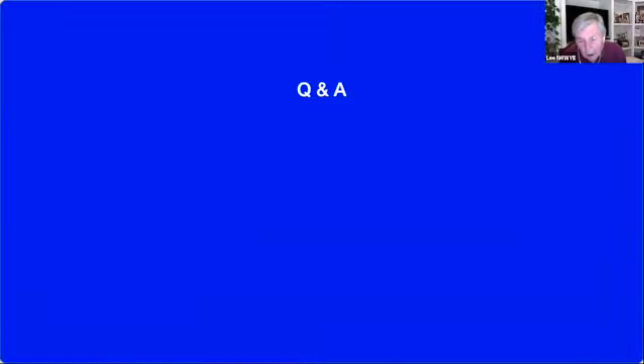Well, the calibration basically takes out the fixed error terms of the actual device, and those aren't something that age. So once you calibrate it, you shouldn't have to recalibrate it. It won't drift out of calibration. Okay. It's as manufactured, kind of, make sure it's all zeroed out. It's kind of like a bridge. Once you zero the bridge out, then you're okay for a while. Actually, I've never recalibrated mine except just for fun to check it out and make sure I didn't need to. I've never seen any difference in the performance of the device using the calibration.